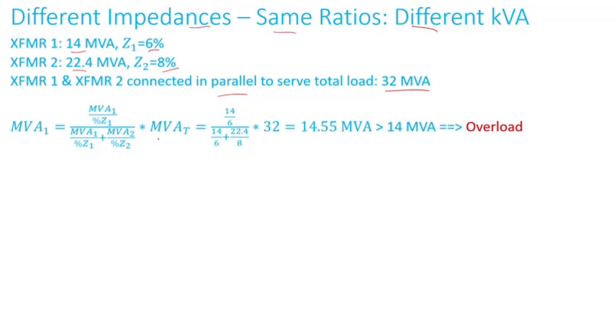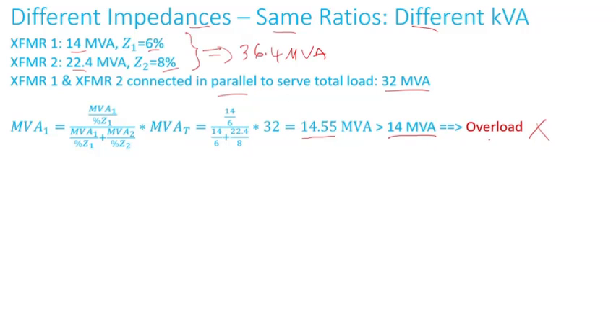Applying the same equation and plugging in the numbers, transformer one will carry 14.55 MVA, which slightly exceeds its rating of 14 MVA. So transformer one will be overloaded. Notice the total capability of both transformers combined is 36.4 MVA, and at a load of 32 MVA — well less than 36.4 — I'm already overloading transformer one.